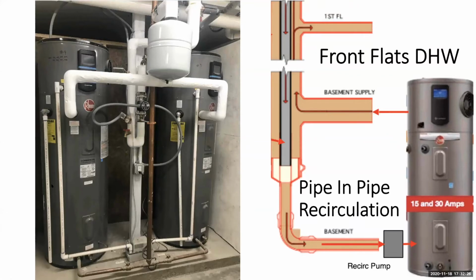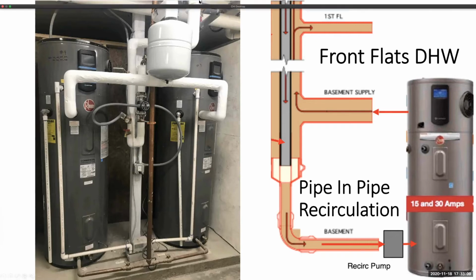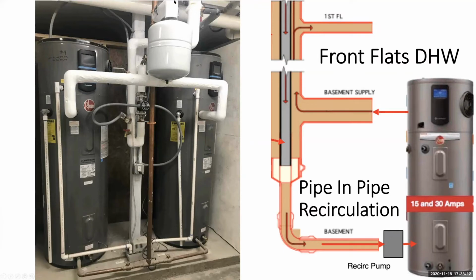So what you have is a vertical pipe going straight up through 4 stories of the building, with just an arm off of it each direction to apartments. There's a wet stack of apartments going up and down. And then when the pipe gets to the top, it turns around and goes back down in the same insulated sheath. In that way, it is giving heat back to the water that's coming in. And what it's not doing is giving heat to the rest of the world, because when you start circulating it along walls between apartments, you dump heat into the outside world and into apartments too, and that's no help in the summertime. So in this way, you reduce heat loss by keeping a very tight loop up, curling right back down in the same insulated sheath.